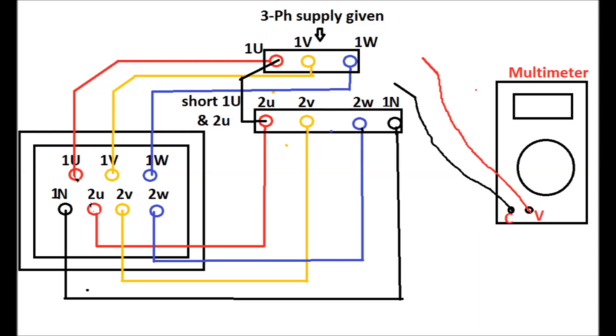Here, 1U, 1V, and 1W are connected using color-coded wire and three-phase supply has been given to terminals 1U, 1V, and 1W. Similarly, the secondary winding and neutral are taken by color-coded wire, and 1U and 2U are shorted at the shorting terminal. We then use a multimeter where C is the common point and V is the volt point to measure different voltages.